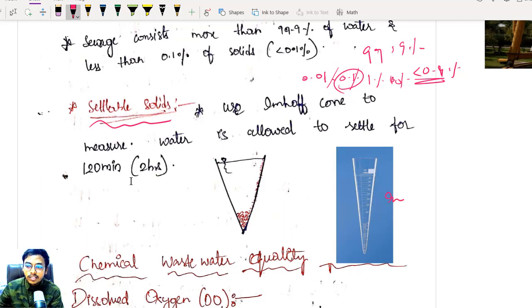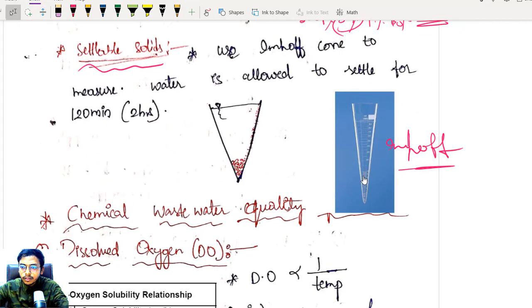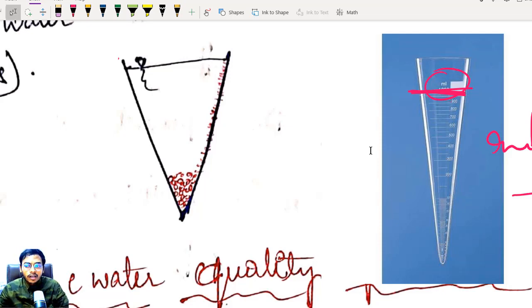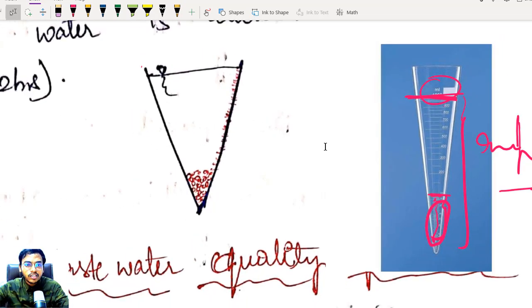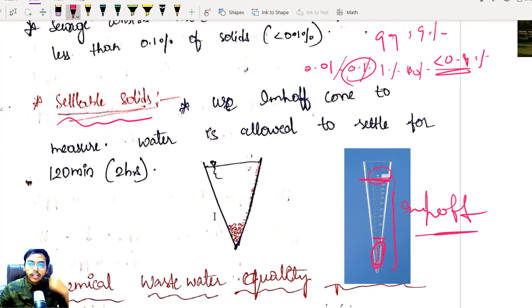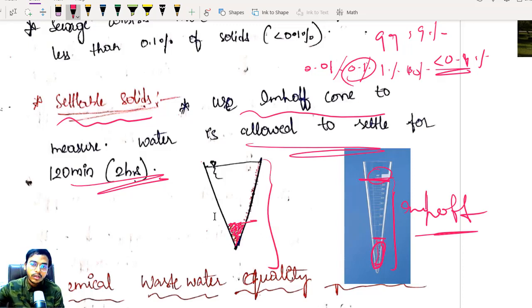To measure settleable solids, we use an Imhoff cone — a one-litre cone. You fill wastewater up to the mark, mix it well, and then the solid content will settle down in this cone with respect to time. The time allowed for objects to settle is two hours (120 minutes). We measure how much solids have settled in the one-litre solution. The instrument is the Imhoff cone and the settling time is 120 minutes or two hours.